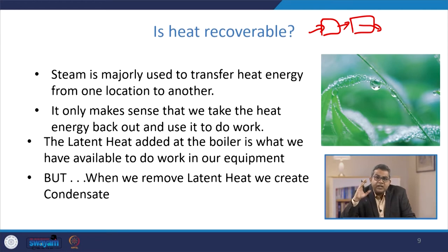all those things. So, the latent heat is usually added at the boiler level, and that is what we have available to do work in any kind of equipment. But another thing is, when we remove the latent heat, we create the condensate. Remember, condensate always possesses an extensive amount of economic value, because whenever we are generating steam from water, we need to have the water in a purified form, and that does cost. We need to perform demineralization and deionization operations, just to prevent the formation of scaling.